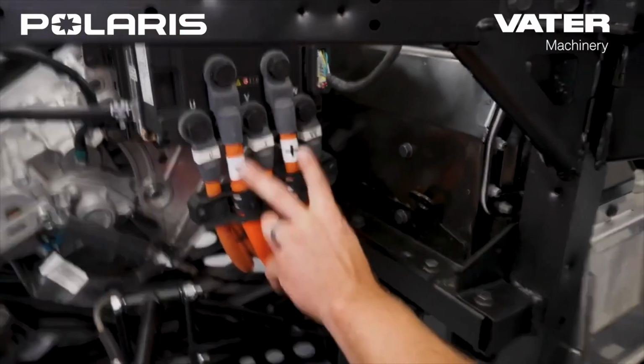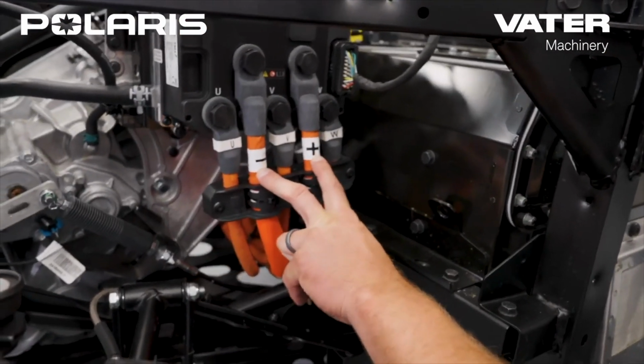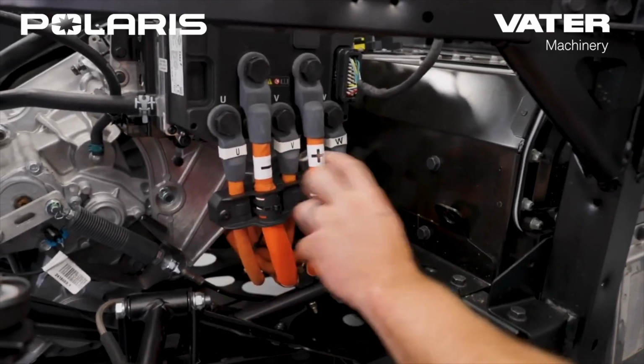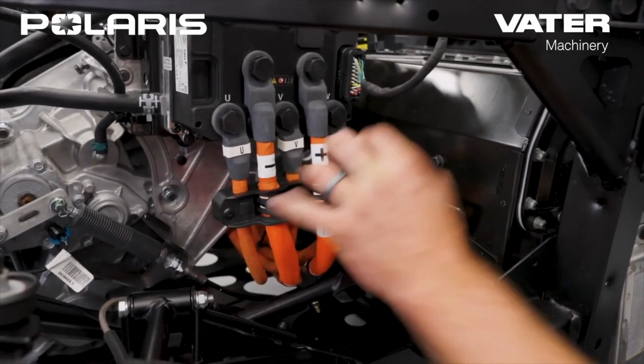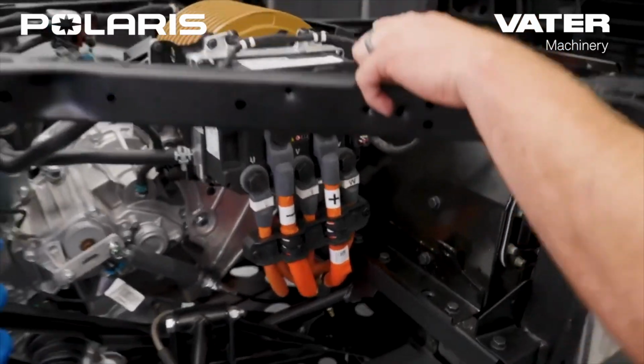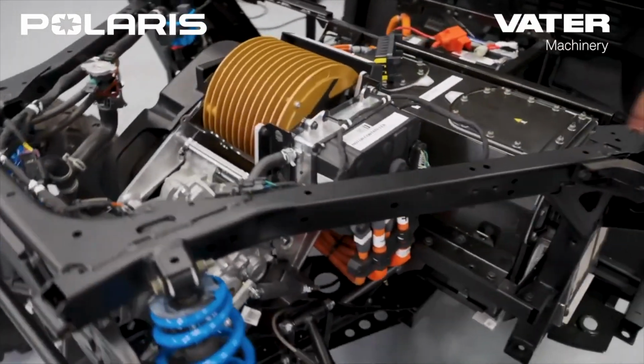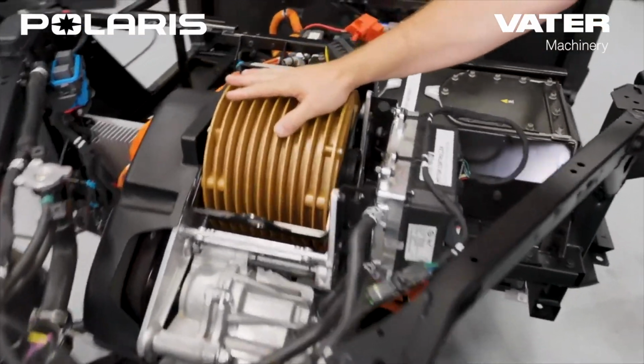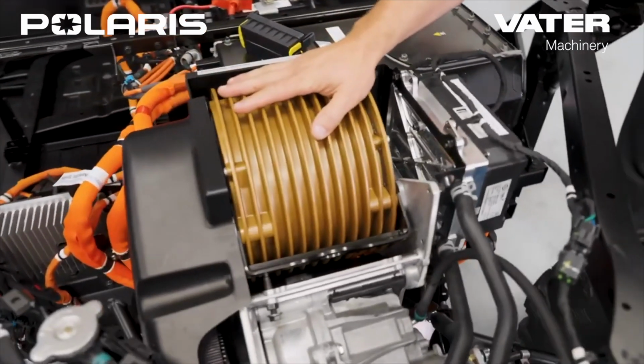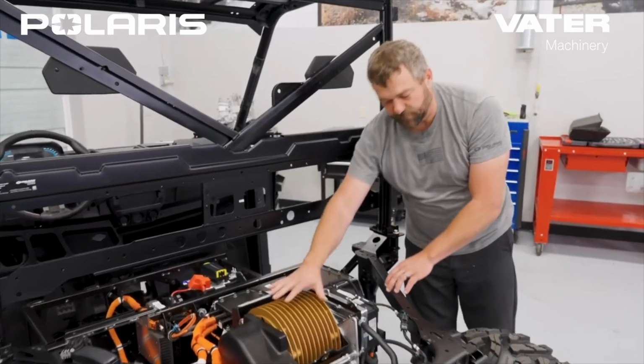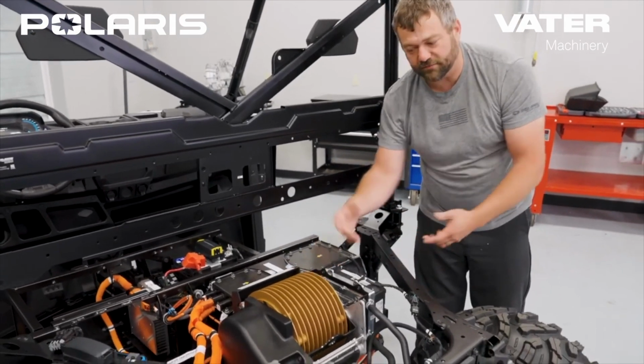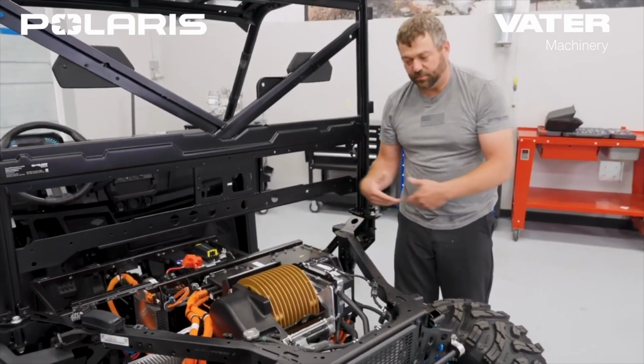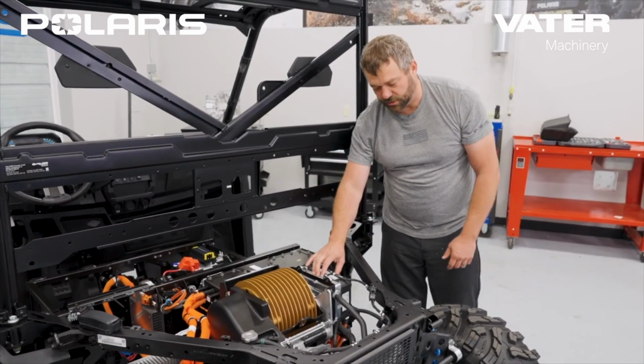You can see we've got plus and minus coming into the motor controller here, so these two are the 100 volt DC bus. Then you've got the three phases, U, V, and W. Those three cables are what's feeding that motor, a three-phase AC induction motor, into this pancake motor here. So basically this thing is going to vary the frequency to drive that motor at different speeds.